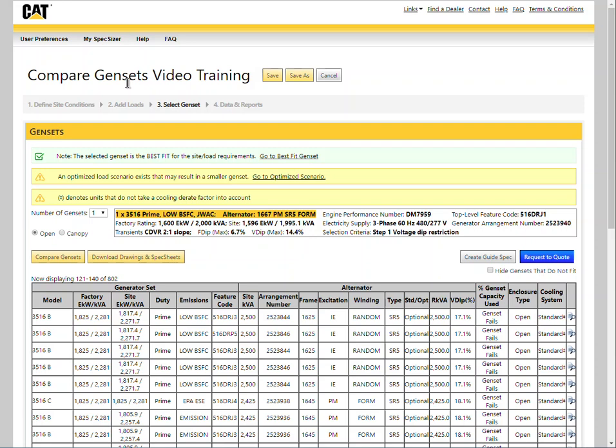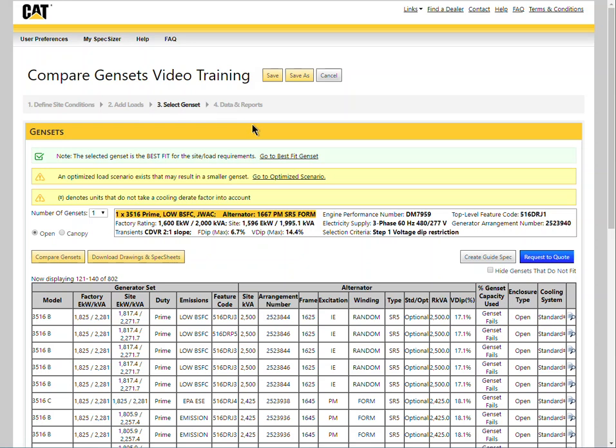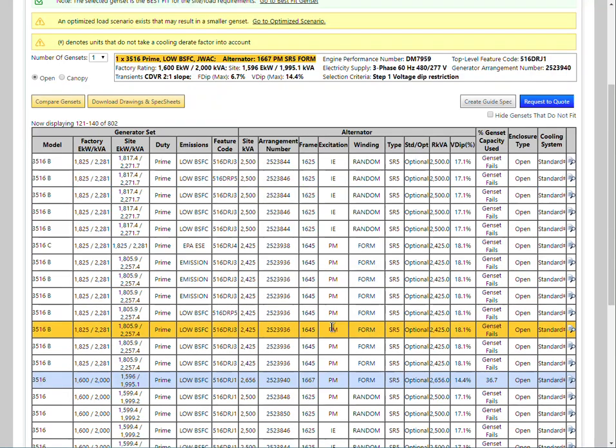Prerequisites to comparing generator sets is creation of load scenarios covered in add loads training and optimizer training. This example uses a pre-existing scenario where the original best fit generator set selected is a 1600 kilowatt 3516 with a 1667 frame alternator at 36.7% capacity used.